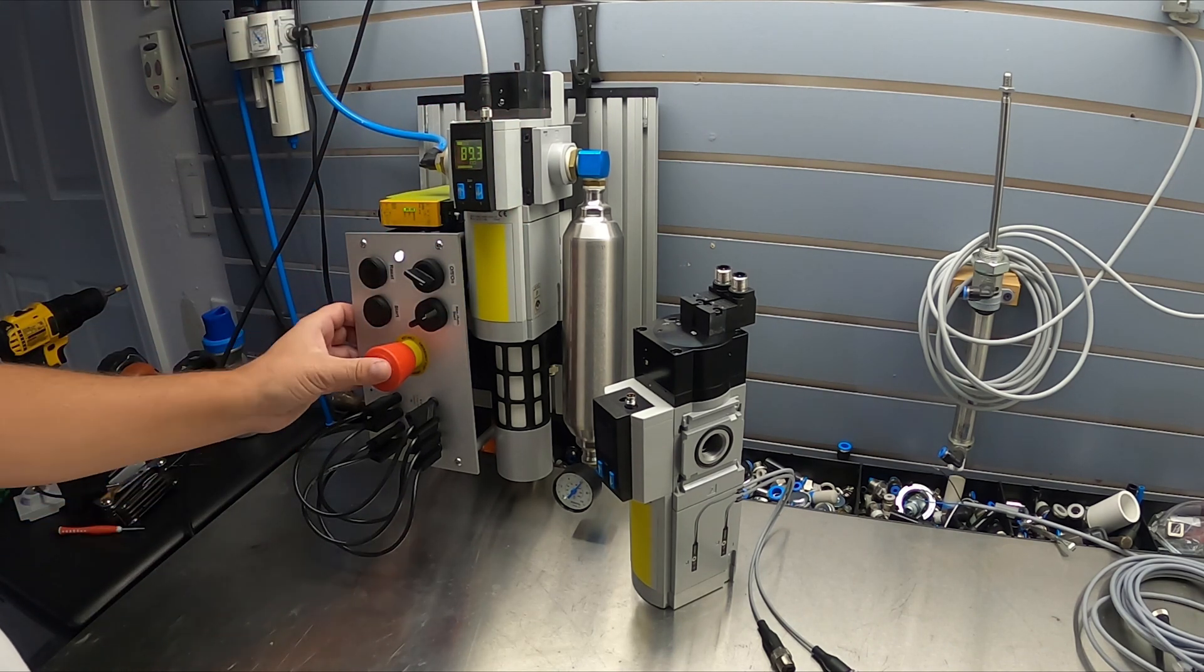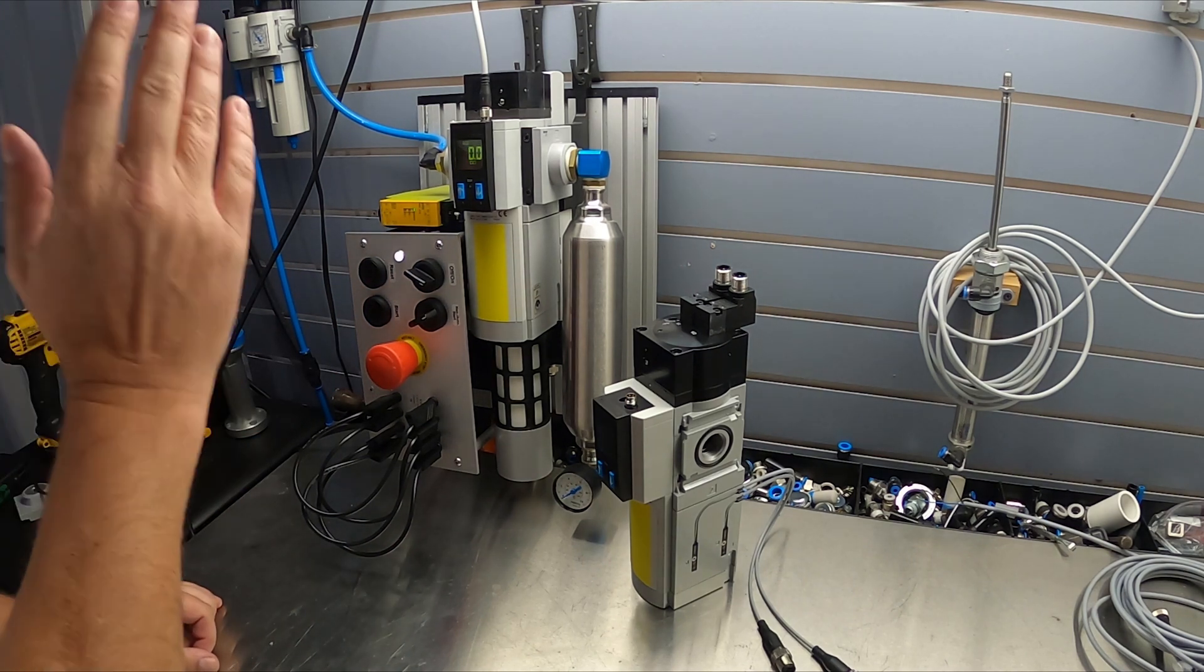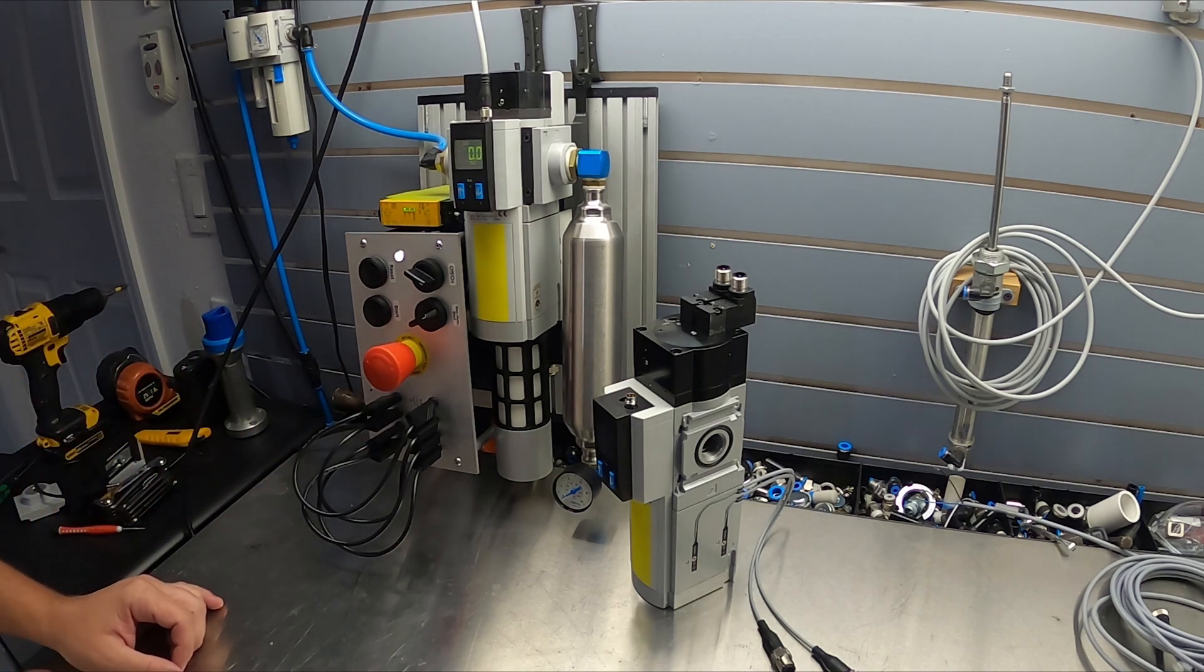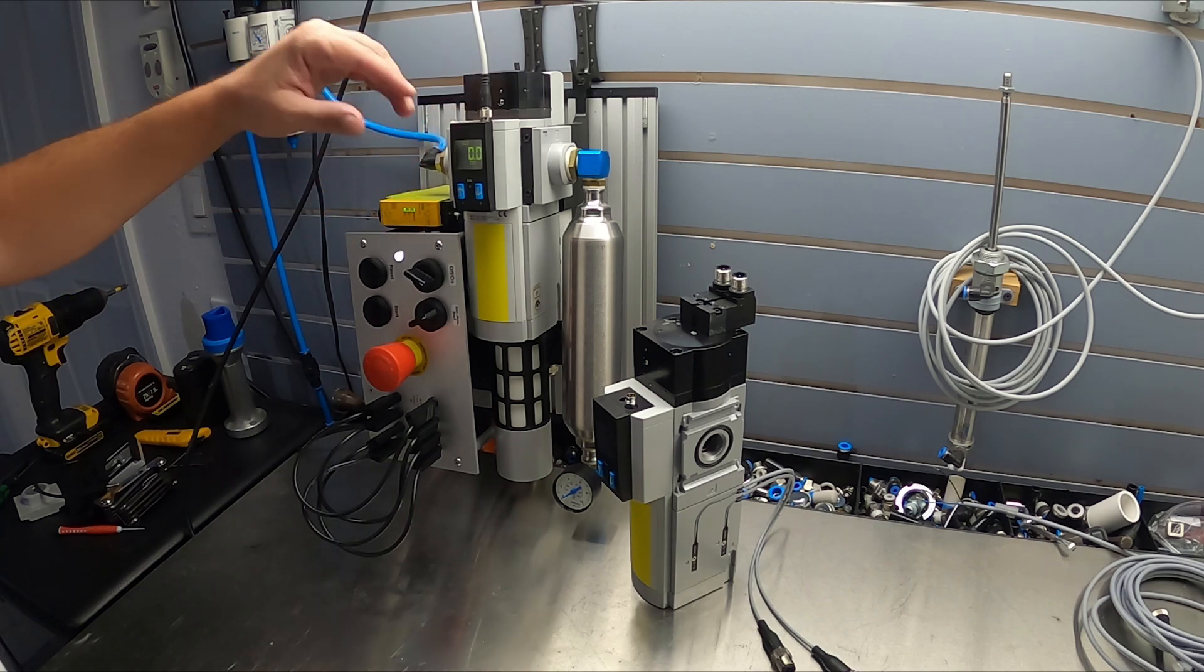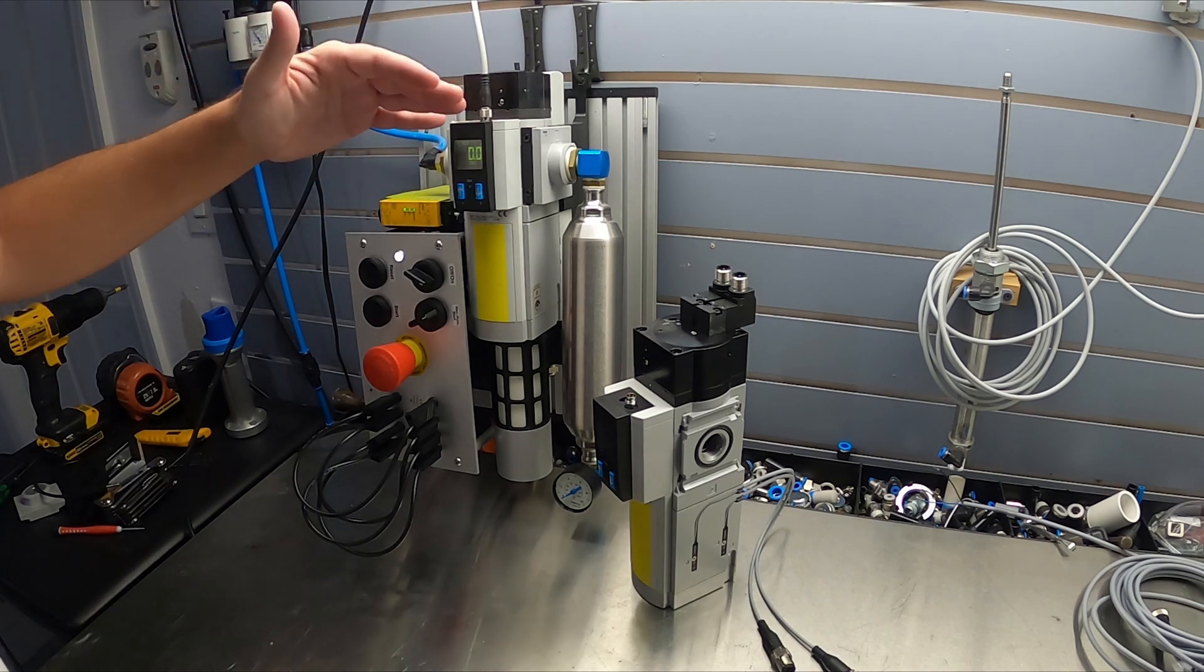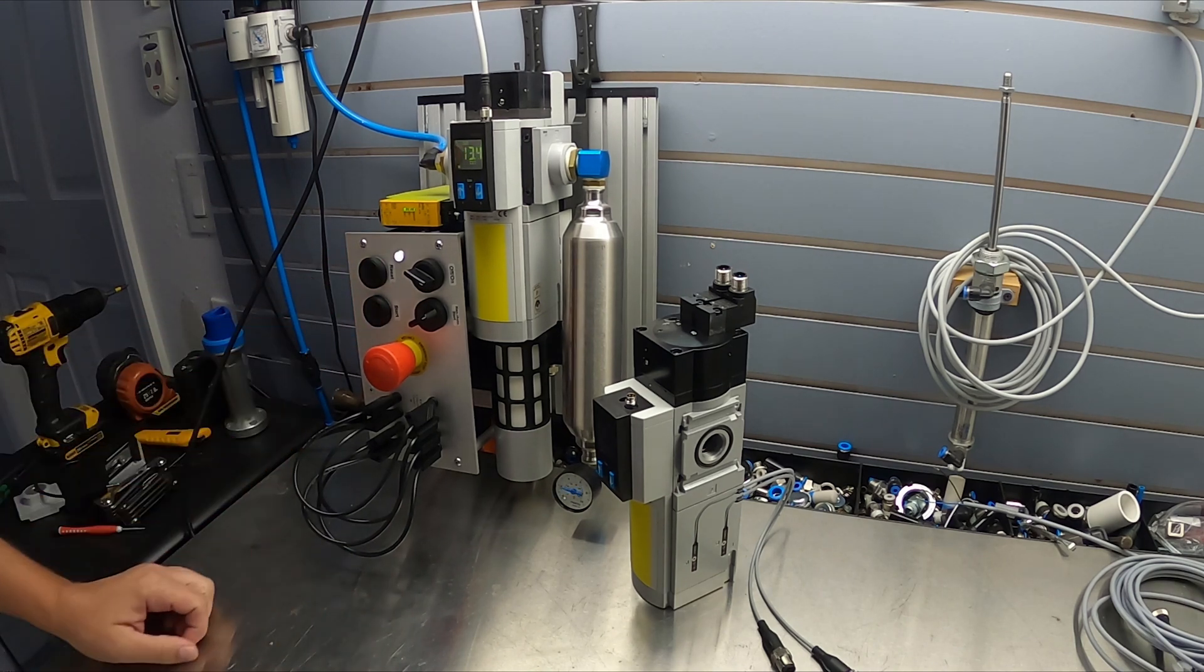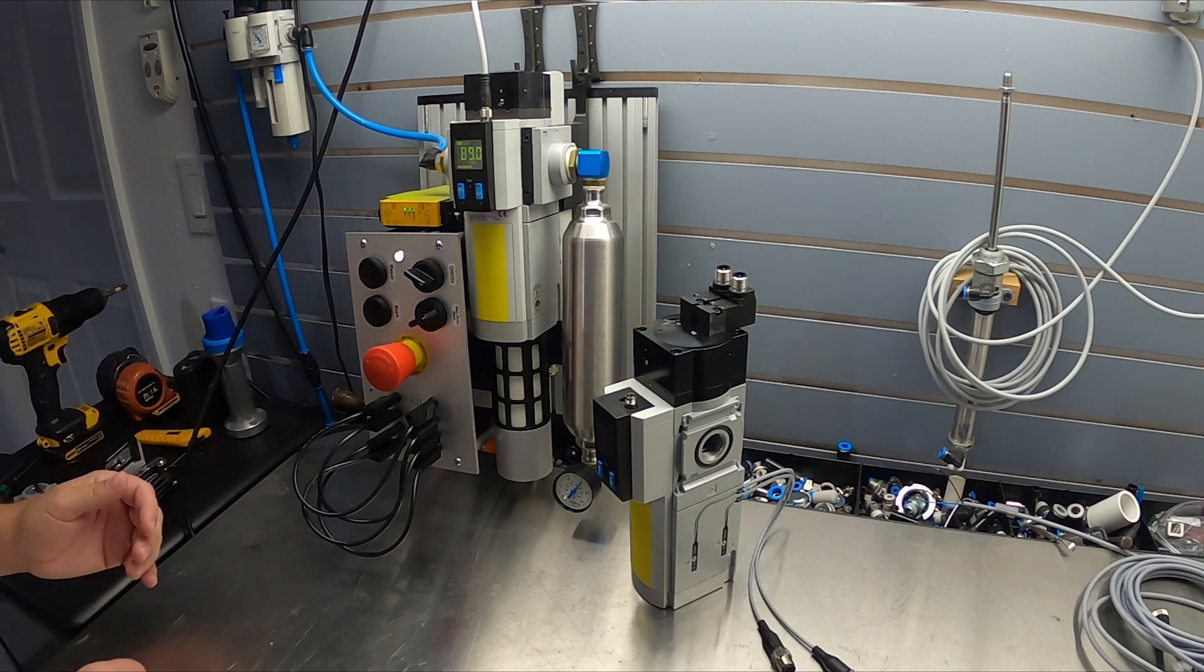E-stop. E-stop's pressed, air is dumped as it's supposed to. E-stop is reset and the relay over here is reset, but the downstream pressure still needs to be manually turned on. So I have to press it again manually and then the pressure goes downstream. So that's manual mode, pretty basic stuff.